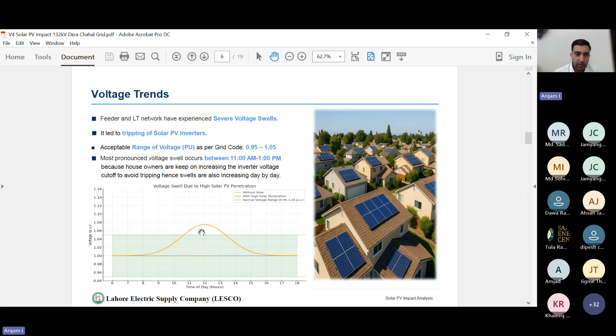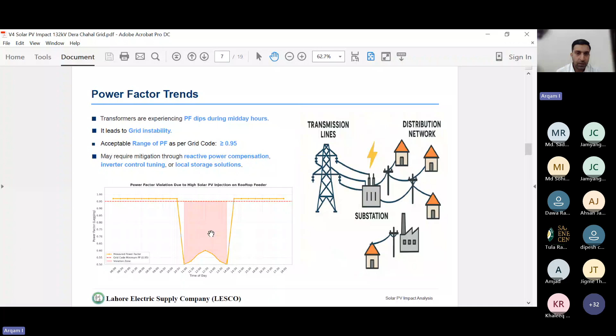So during the day hours, once we have massive solar PV generation, the power factor at the substation dips to 0.5, 0.6. All the reactive power is being supplied from the grid, and the active power is generated from the rooftop PV systems, which is consumed by the loads connected to the PV systems. So all these challenges are becoming more and more critical, with reverse power flows, overvoltages and power factor dips.